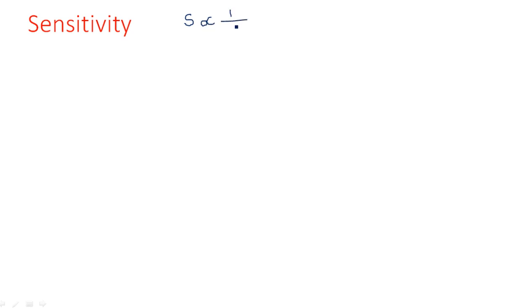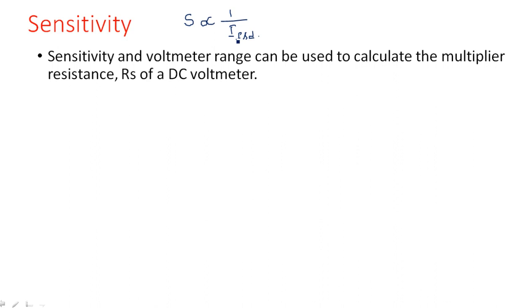Coming to sensitivity. Sensitivity of a voltmeter is defined as proportional to one divided by the full scale deflection current. Sensitivity S = 1/IFSD — it is the reciprocal of the full scale deflection current. Sensitivity can also be used to calculate the multiplier resistance RS of a DC voltmeter using the formula: RS = S × range − RM.